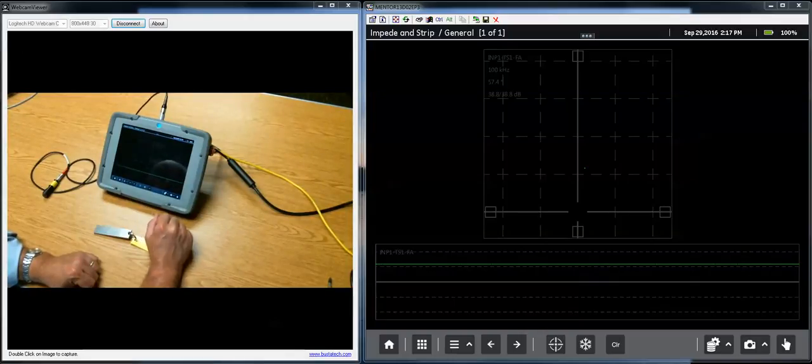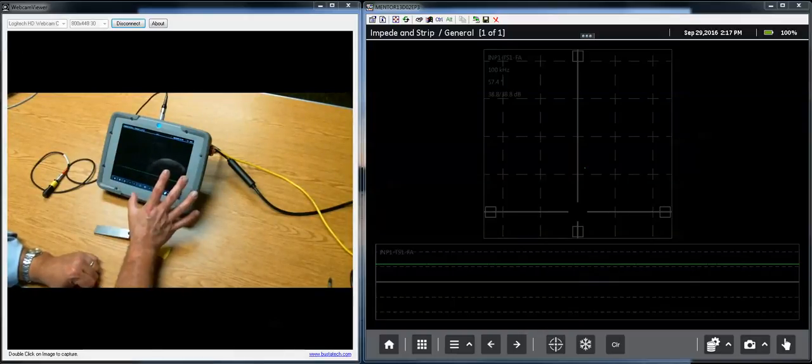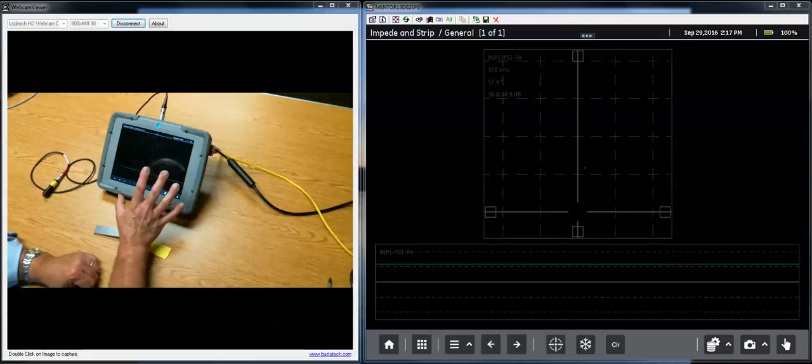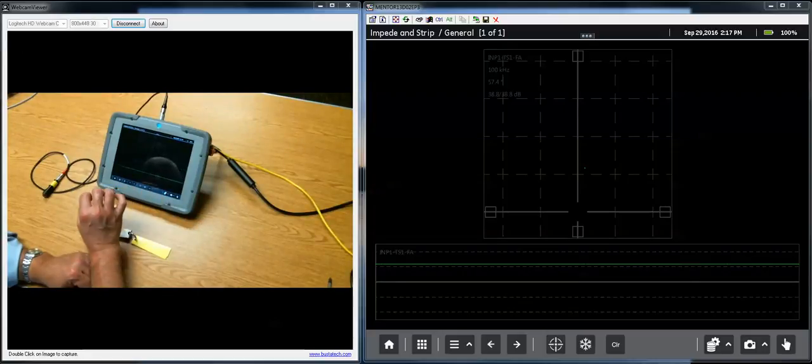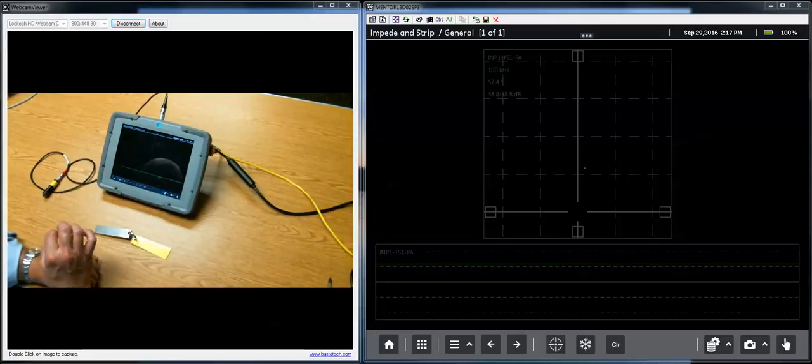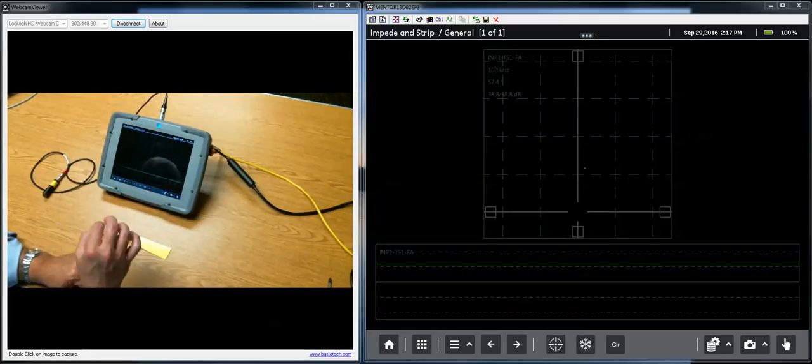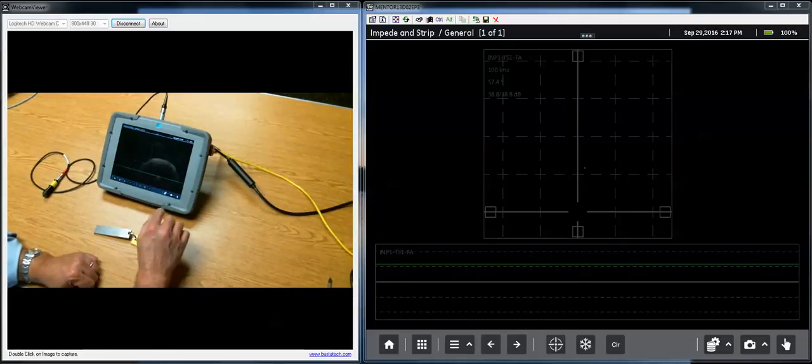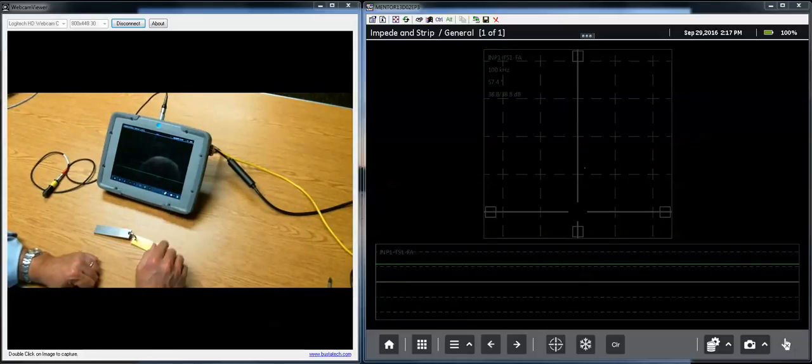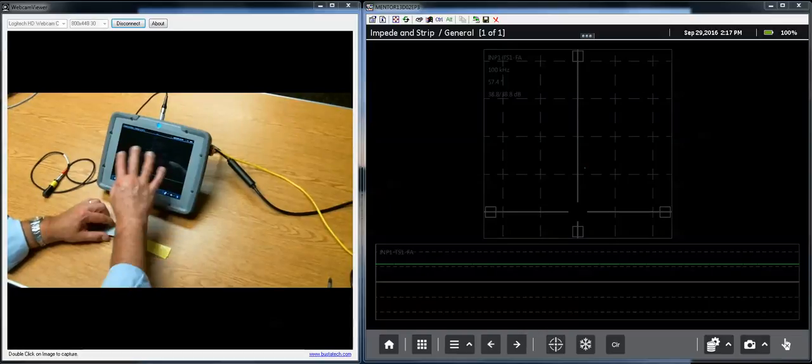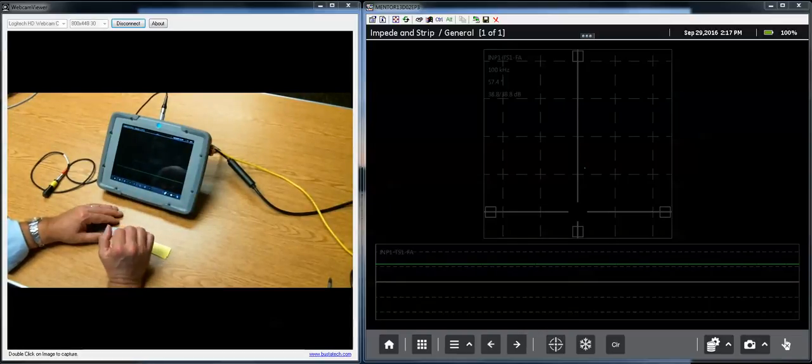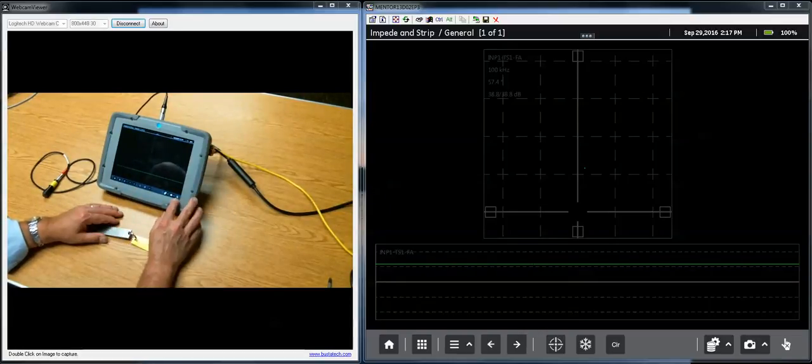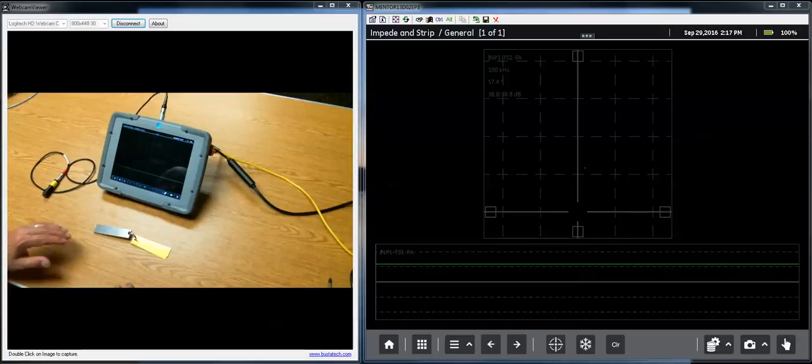However, once you've gone through your process of calibrating for a specific test and you're, say, up on the wing of an aircraft inspecting a rivet line, you might want to think about locking your display, locking your touchscreen, so that you don't accidentally change something about your setup in the middle of the inspection.